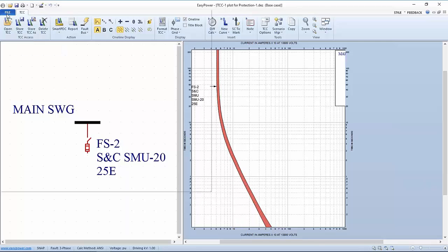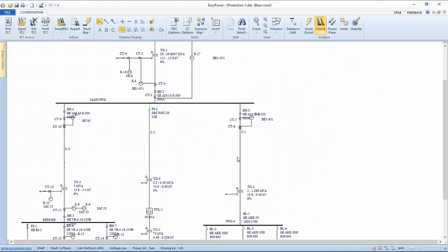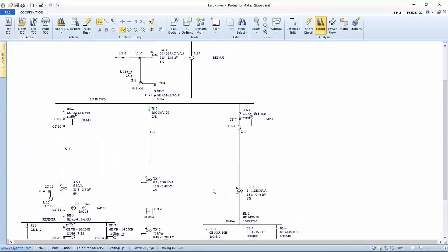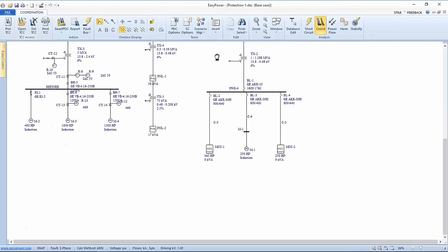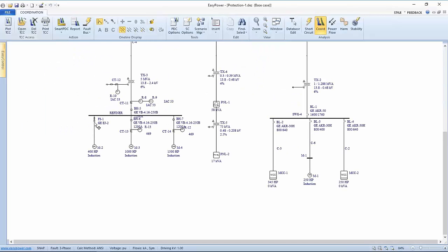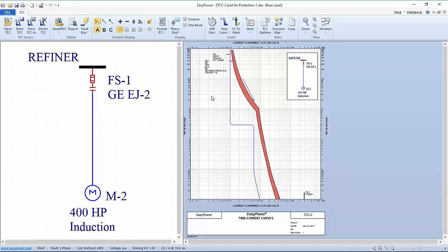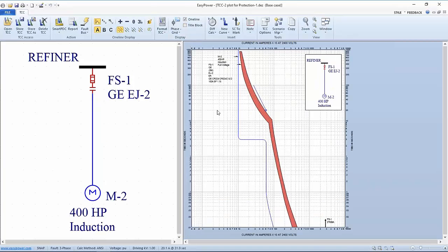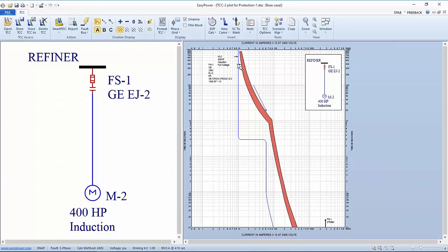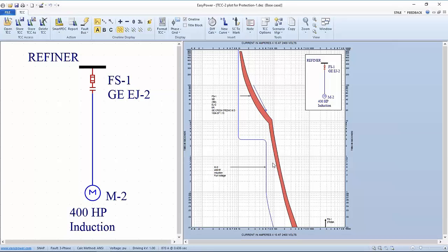The left-hand side of the curve is the minimum time that the fuse can clear in. The right-hand side of the curve is the expected time the manufacturer pretty much guarantees the fuse will work. If we look at this particular current of 100 amps and we take it up to the point where it intersects the curve, the manufacturer data sheet says that this fuse will blow or clear the fault of 100 amps in 2.76 seconds. Now the tool, the benefit of the tool is if I can plot the motors or the transformers that this fuse is protecting, as long as the operation of the motor is going to be on the left-hand side, then that means the fuse won't interfere with the total operation of the motor.